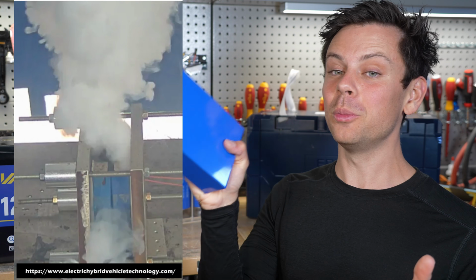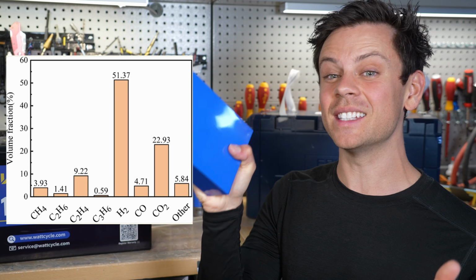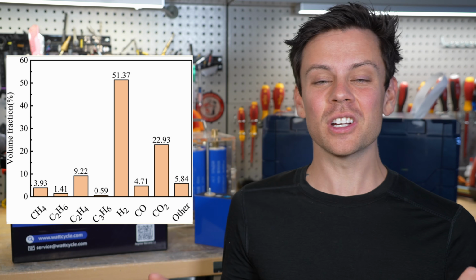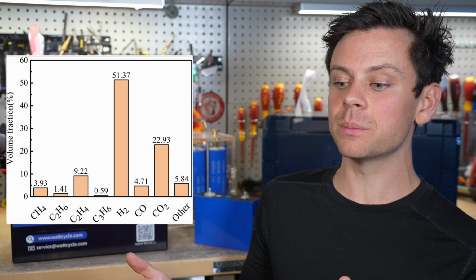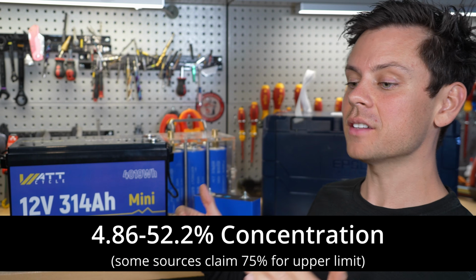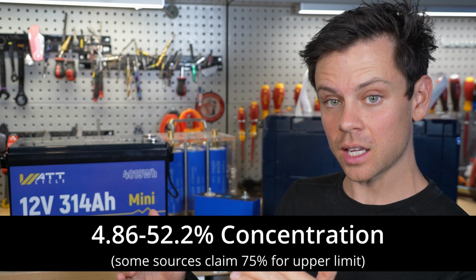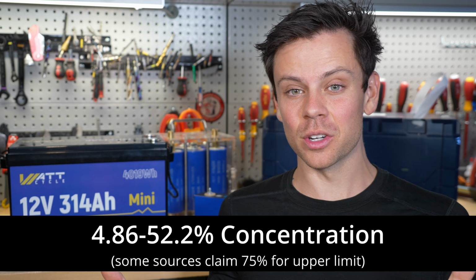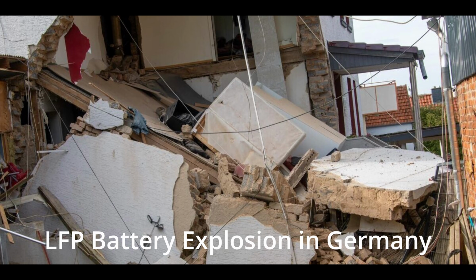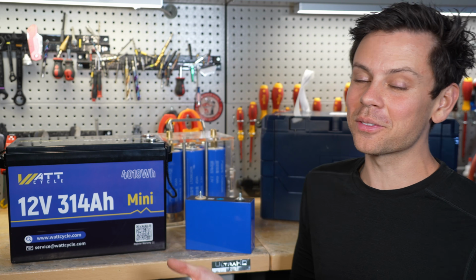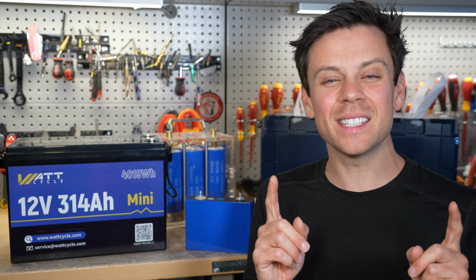By volume, almost half of the gas this creates is hydrogen. If that hydrogen accumulates in a small room, a basement, or even a boat, and the concentration goes above 4%, and there's an ignition source, you're going to have an explosion. Technically it's pretty hard for this to happen, but it could happen to any battery.